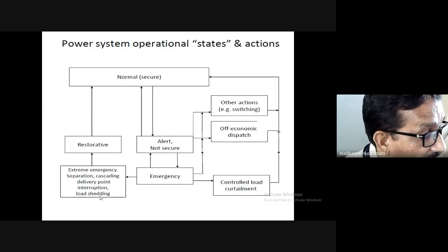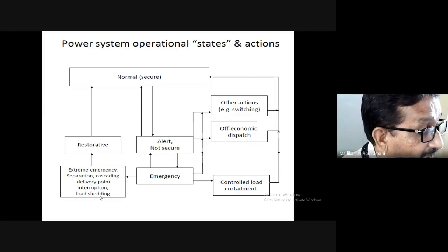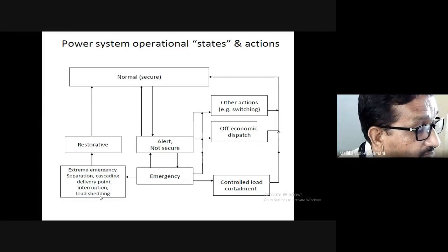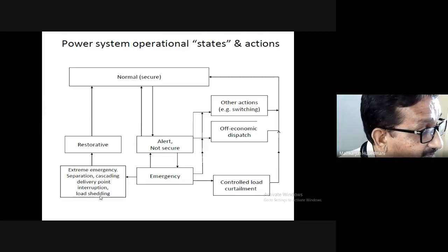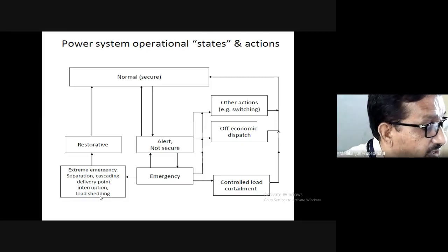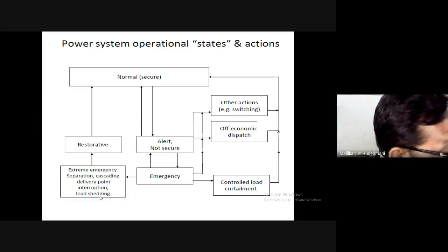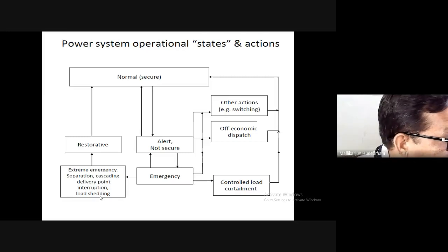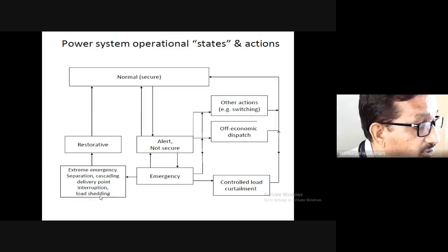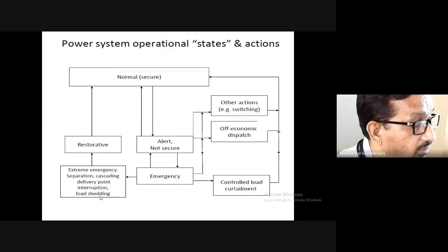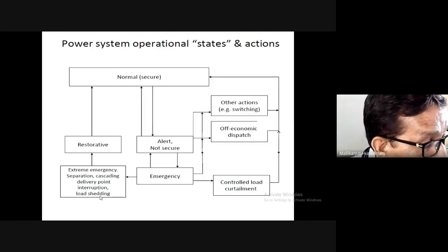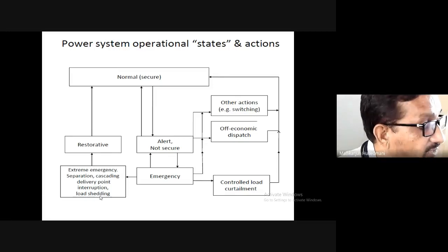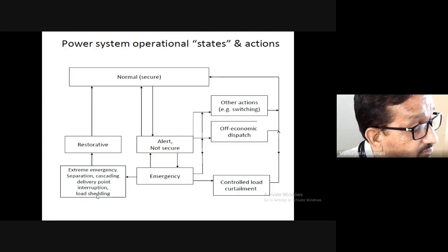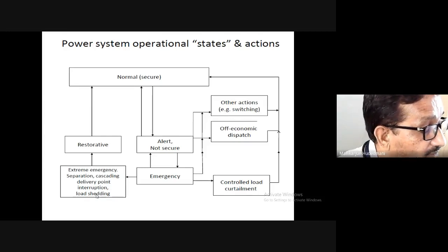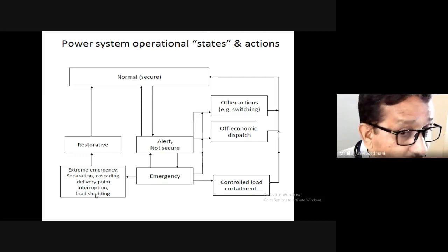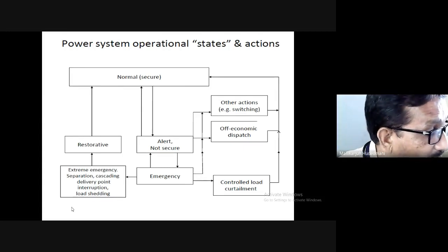Think of a geographical disaster, a natural earthquake or flood situation, where an islanding situation results. A generating station is intact, generation is going on, but there is no one to deliver the power because the transmission line is broken, or the receiving station has totally gone out of control, damaged due to the disaster. So it is not receiving the power, so how can you distribute it? Or generators may have been washed away in the flood. Then there is no generation at all, but there is load, there is transformer mechanism, or there is a substation available. Likewise, islanding is possible.